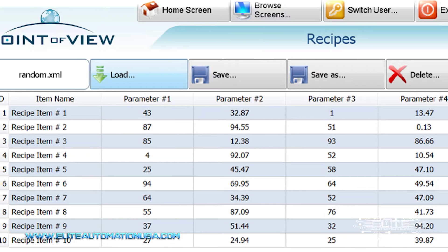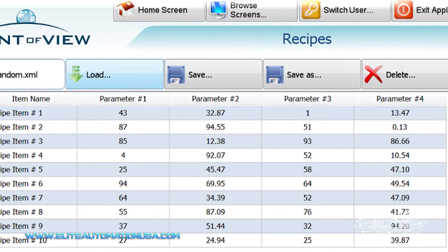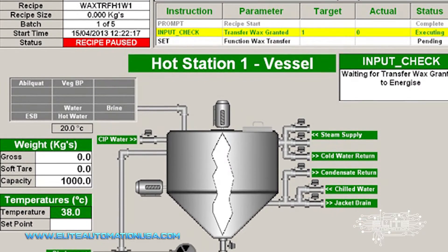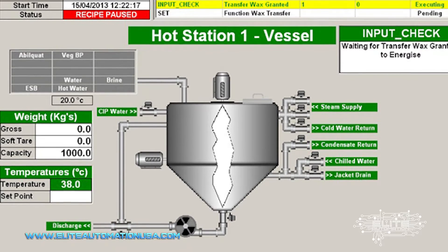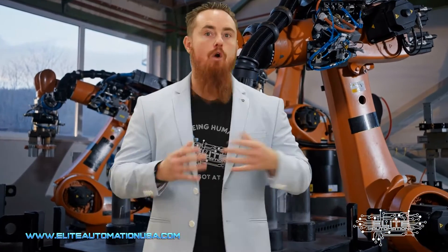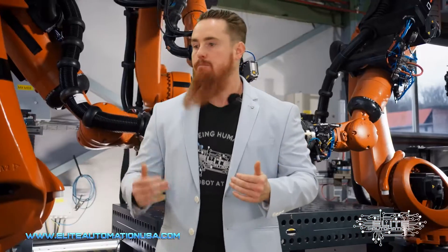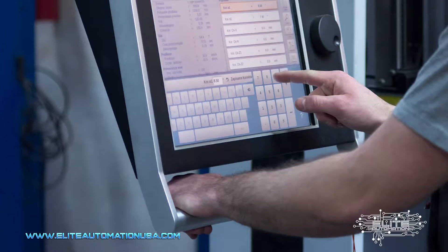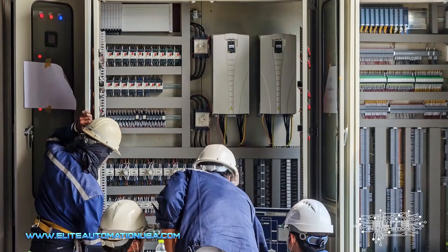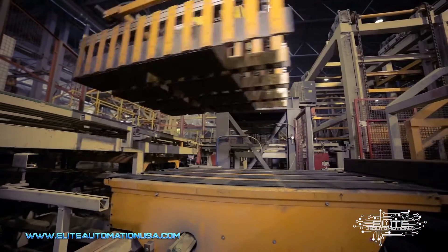On the HMI you can change variables like cycle times, conveyor run times for bigger or smaller parts, or the color of the product so the system can reject or flag an alarm if the wrong color is run. Going back to the robot tooling example: part number X uses tool one, part number Y uses tool two, part number Z uses tool three. A programmer takes that HMI data, saves it into the PLC, and passes it off to the robot.